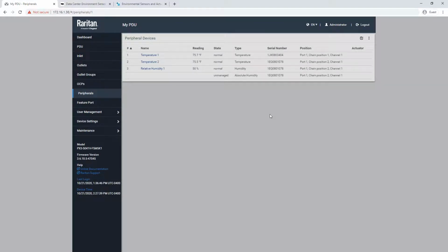But we'll ignore that for this demonstration, and I'll chain my last temperature sensor to this PDU. That pops up as temperature 3. They all have their readings here, and on the position, it tells me what port I'm plugged into. On a PDU with an IX7 controller, I only have one sensor port, so it's going to be port 1.